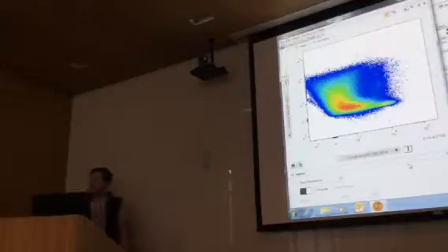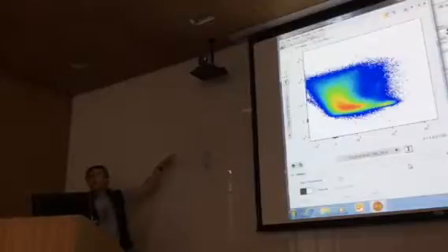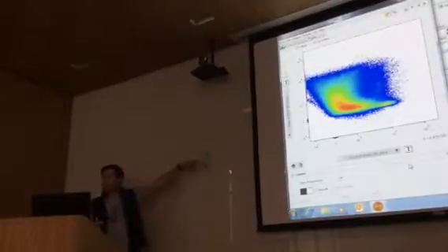So the voltage of the PMT, so it's not just the color of it, but it's actually the voltage at which you are detecting this particular color, and the intensity at which this color is at also plays a huge role in determining the compensation.